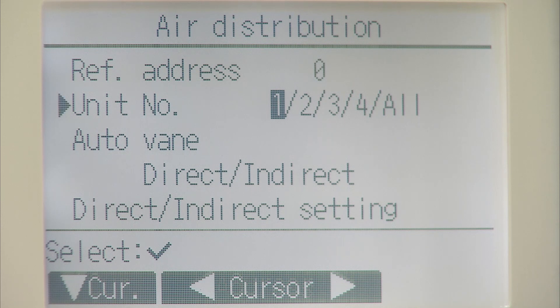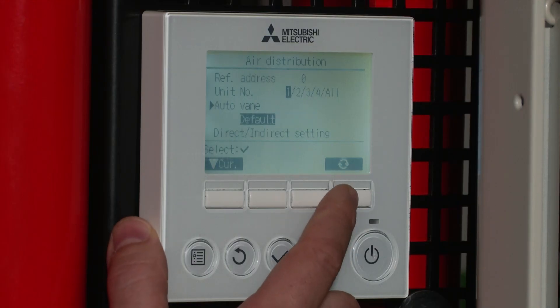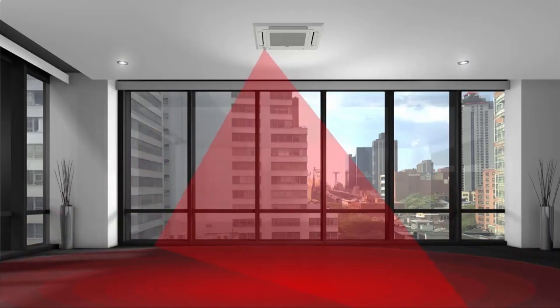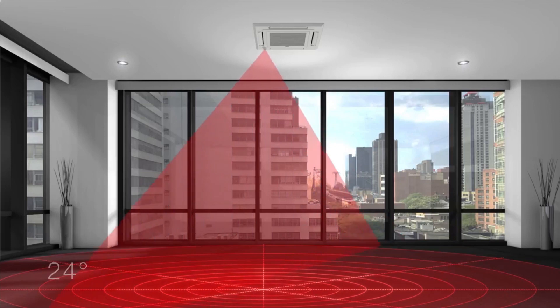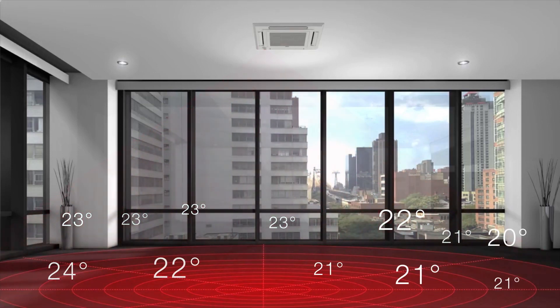Scroll down to auto vane and we can select through these options. The first one we'll discuss is area. With the area option, the unit will look at the temperatures within the room and work out from that where it needs to blow the air — to the hot spots or the cold spots of the room, depending on which mode the unit is set for.